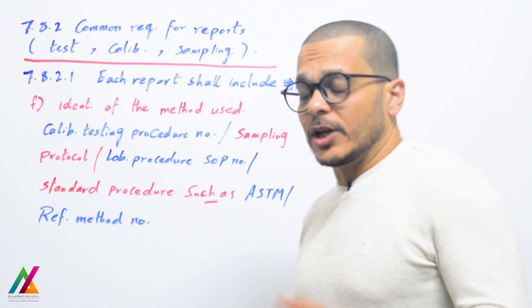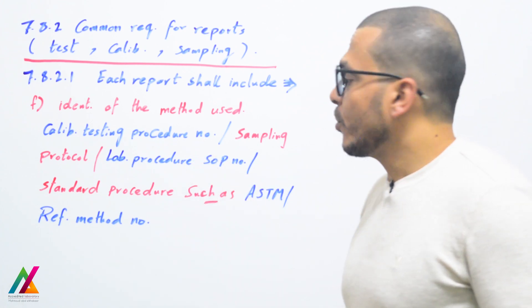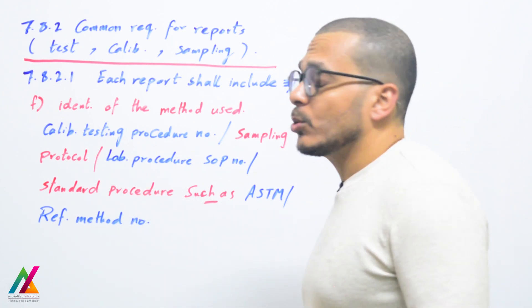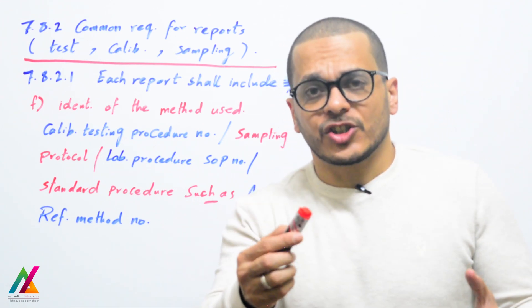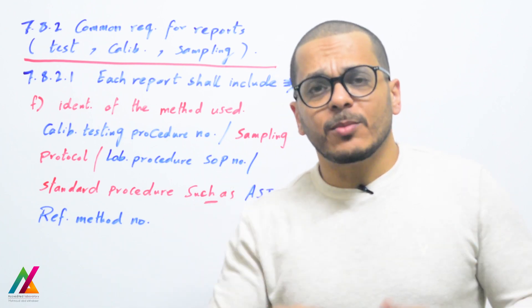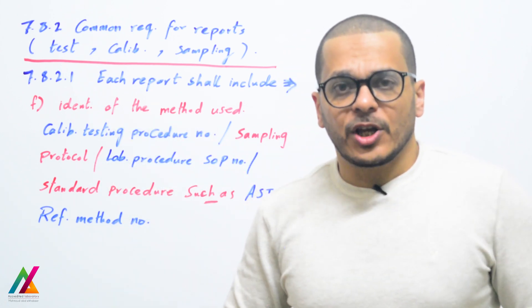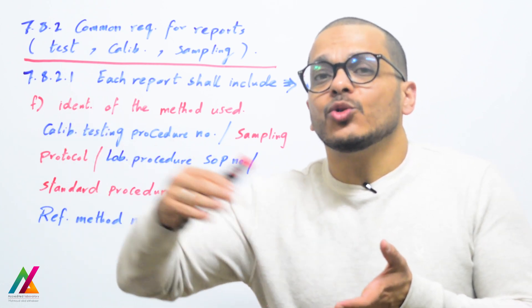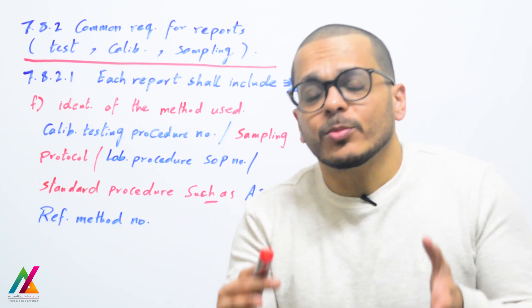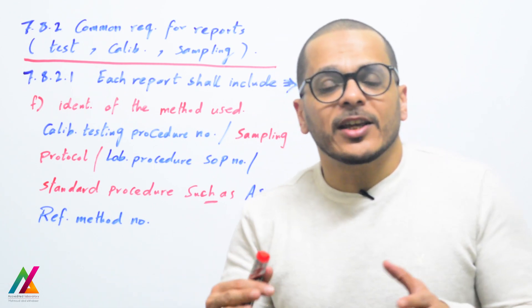The identification of the method used — such as the calibration or testing procedure number, sampling protocol, lab procedure, standard operating procedure number, or a standard reference method such as ASTM — shall also be included in the final report. However, if you have different parameters for each sample, it may be difficult to add the reference method number for each parameter. In that case, this information will be mentioned in your SOPs or quality manual and will be readily available for the customer upon request.